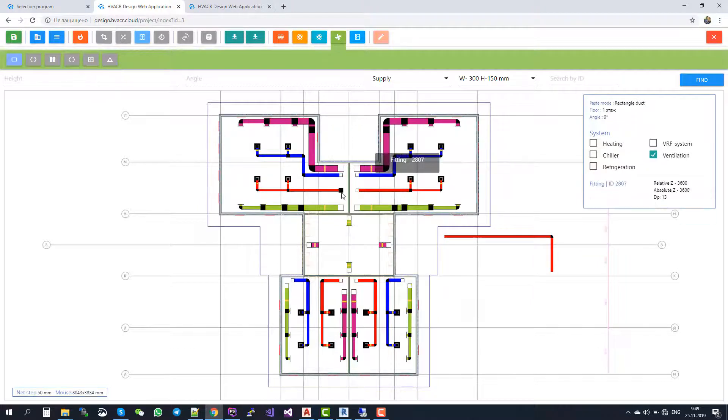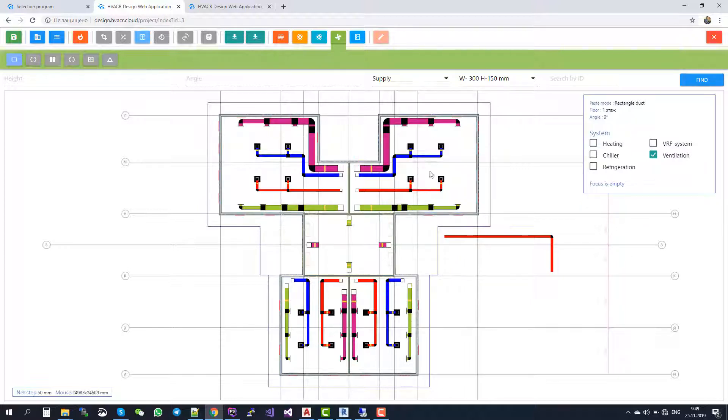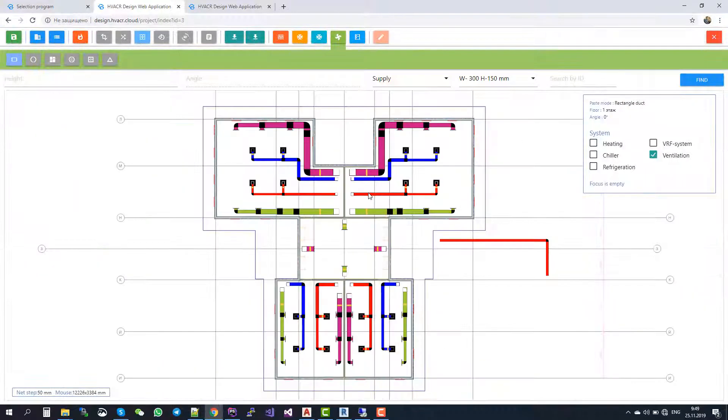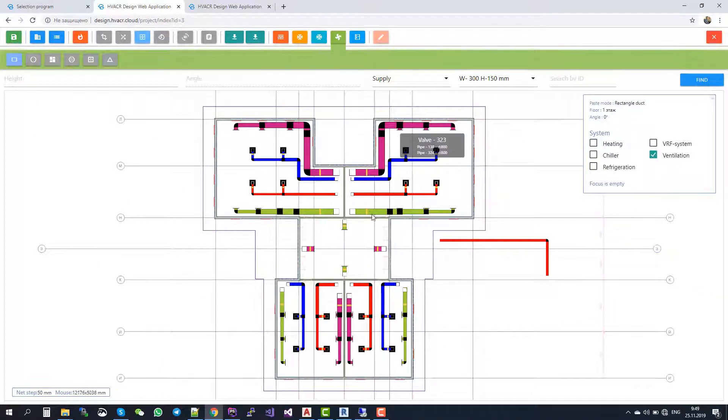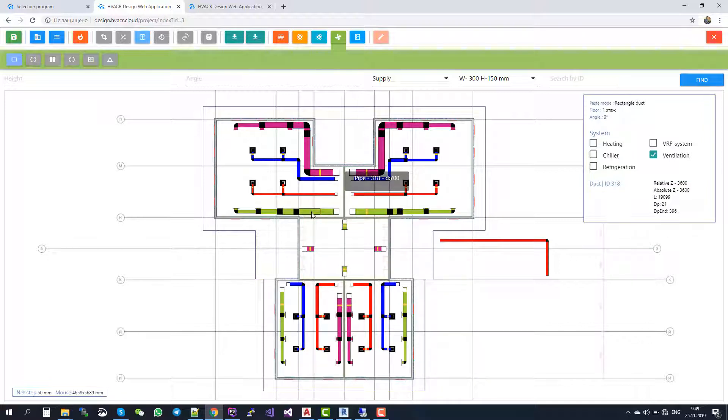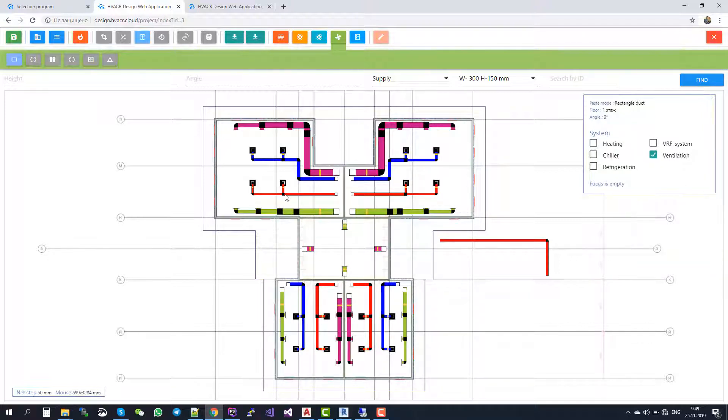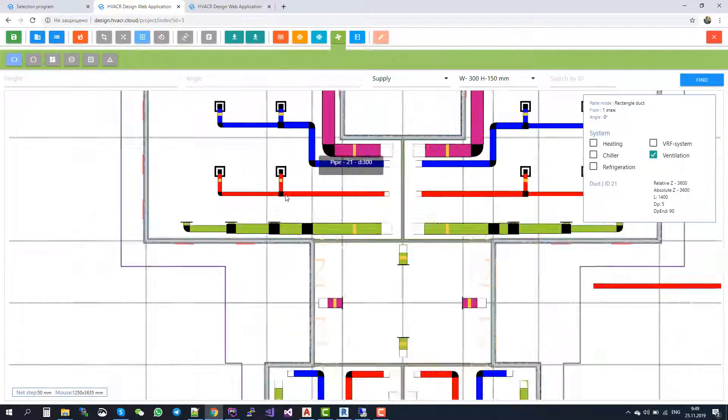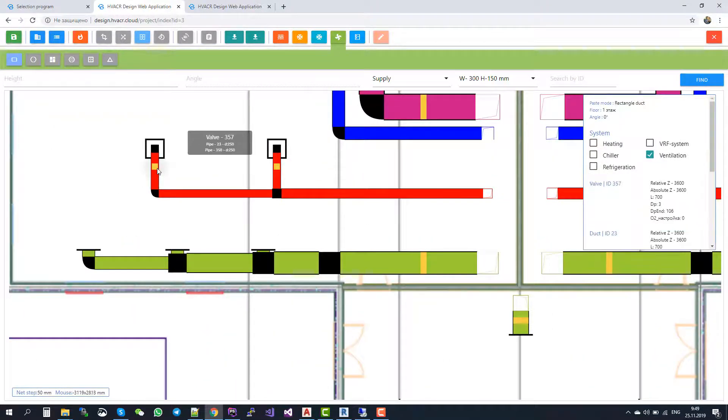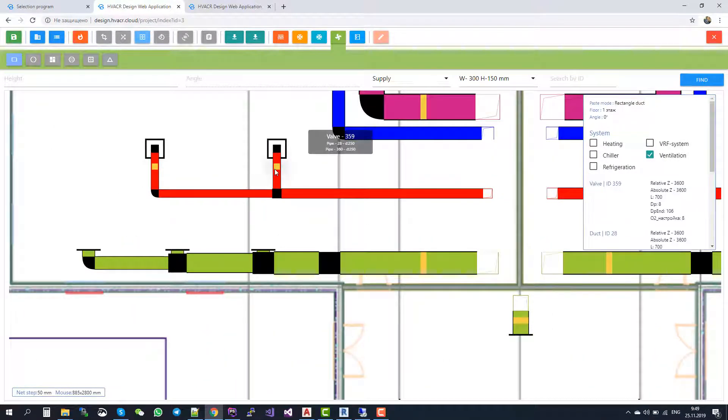In our system, you can both calculate the general Ventilation systems, here they are red and blue, and the smoke removal and pressurization Ventilation systems. By calculation, I mean the sizing of the general Ventilation system and the balancing of the system. By sizing, I mean automatically giving sizes to the ducts. And by balancing, automatically balancing the dampers. Here are the dampers, so they are automatically balanced by our system.